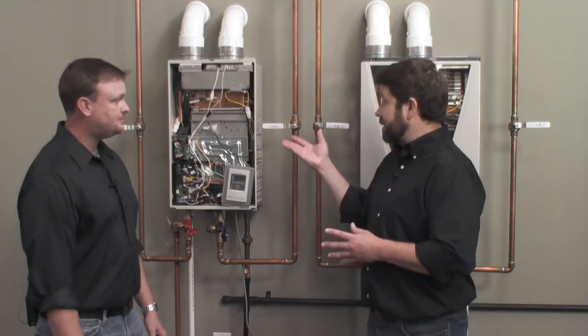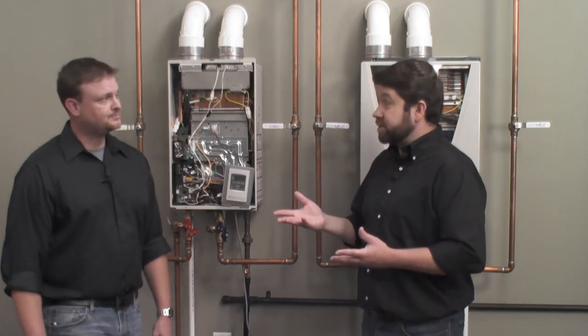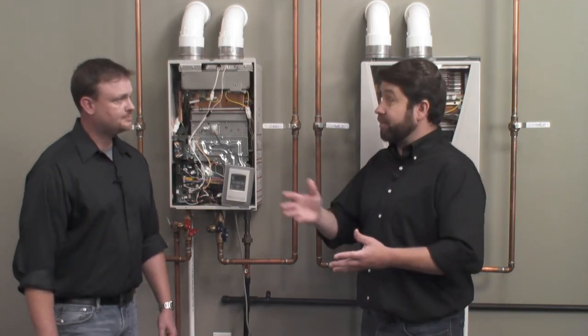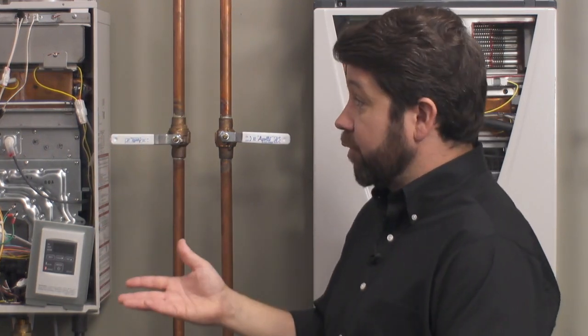Not every application or installation is the same, so the vent runs might be a little bit different. This allows for the different friction for the air, and if we're marginally just a little shy on our gas, it will overcome that. But if we get too far out of that range, it's going to let us know that it can't burn clean. It's going to give you a message that it needs to be looked at.